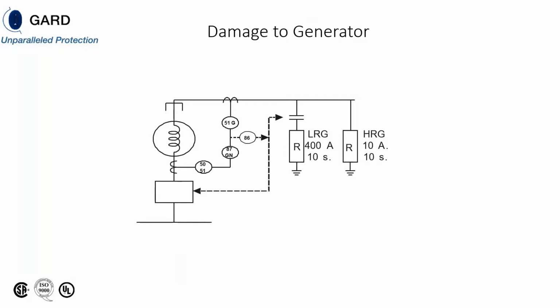For this reason, IEEE formulated a committee in the late 1990s, early 2000s, and they developed a hybrid high resistance grounding scheme. And this particular scheme is what's shown in C37.101, stator ground fault currents or generator ground fault current protection.